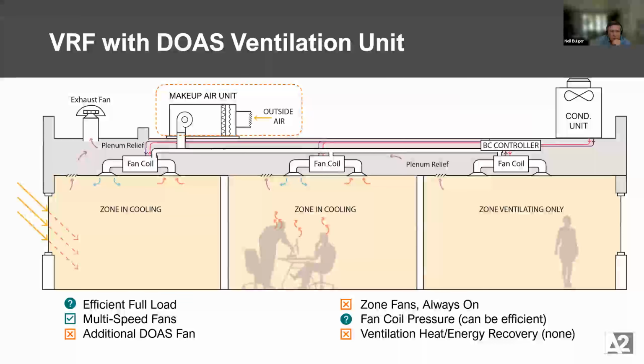If we were to add this makeup air unit and just duct in the outside air, not necessarily even treat the outside air, just bring it into the building. What this does, why I did this in the model, is I really wanted to use these multi-speed fans. And I also wanted to ensure I was getting enough fresh air into the building.